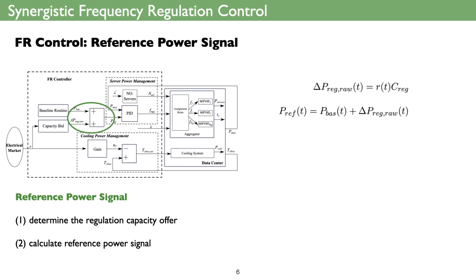So for the reference power signal, there are two functions in this module. The first is to determine the regulation capacity offer. The second is to calculate the reference power signal, as I show in these two equations. The delta P is the power range that the data center should operate within when providing frequency regulation based on the capacity bids C and the regulation signal R. The regulation capacity bids can be determined optimally using the optimal framework that I will talk about later. The delta P is then added to the baseline power to get the final reference power signal that the data center should follow in real time.